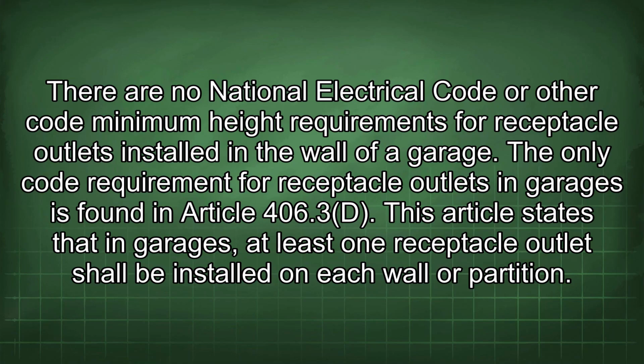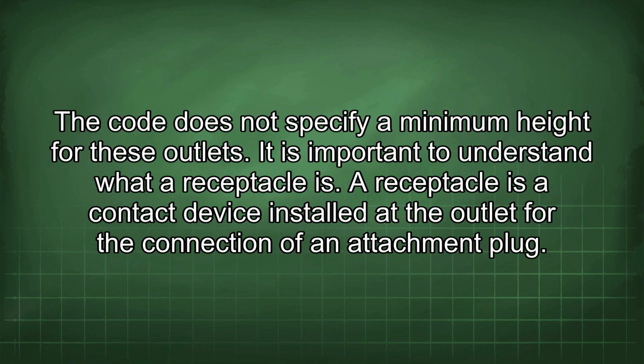There are no national electrical code or other code minimum height requirements for receptacle outlets installed in the wall of a garage. The only code requirement for receptacle outlets in garages is found in Article 406.3d. This article states that in garages, at least one receptacle outlet shall be installed on each wall or partition. The code does not specify a minimum height for these outlets.